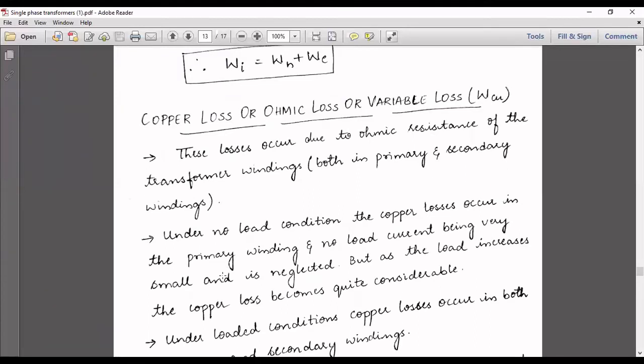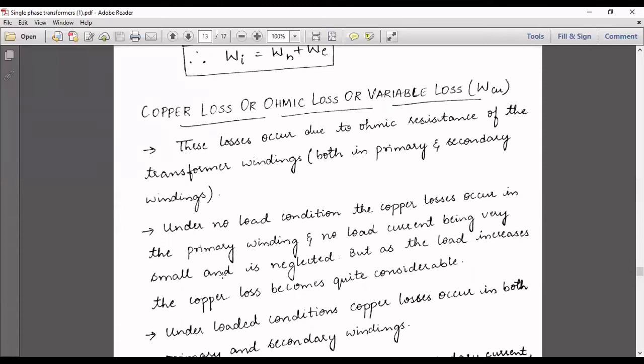So where do we get this copper loss, or ohmic loss, or variable loss? These losses occur due to the ohmic resistance of the transformer windings. Because of the resistance present in the transformer windings, both primary and secondary, copper losses occur. This copper loss is always the I square R loss. Why? Because the power equation is given by V into I. But in the windings, there is a resistance which comes into the picture. So when we express the power in terms of the resistance, VI becomes I square R. That is why copper loss is always considered the I square R loss.